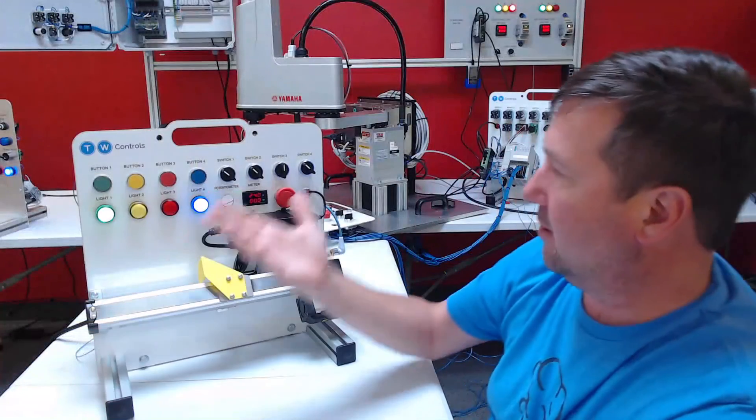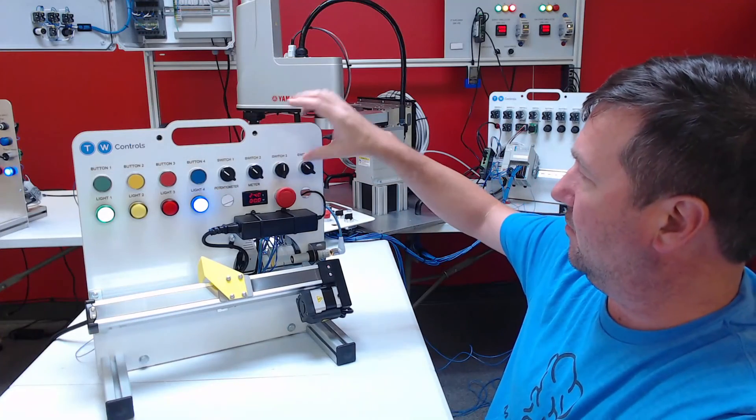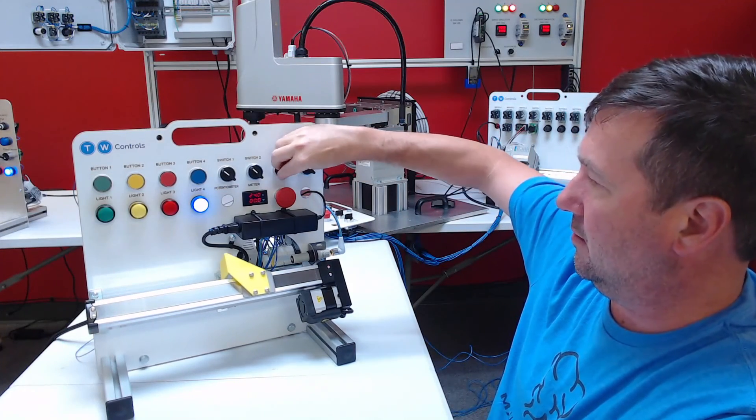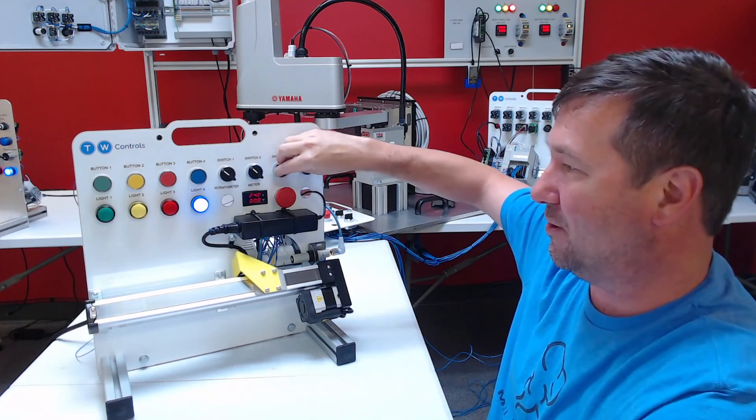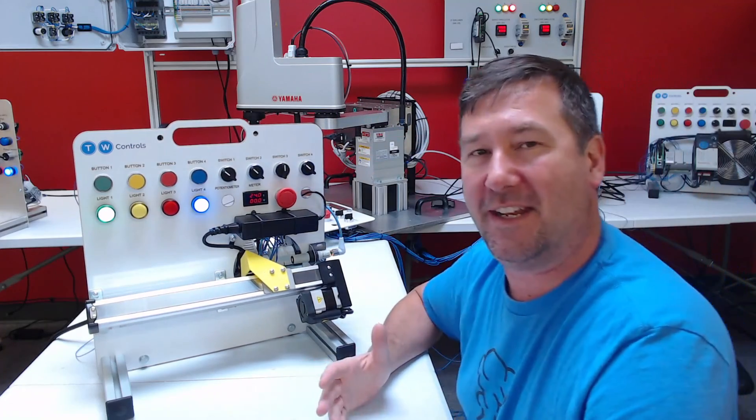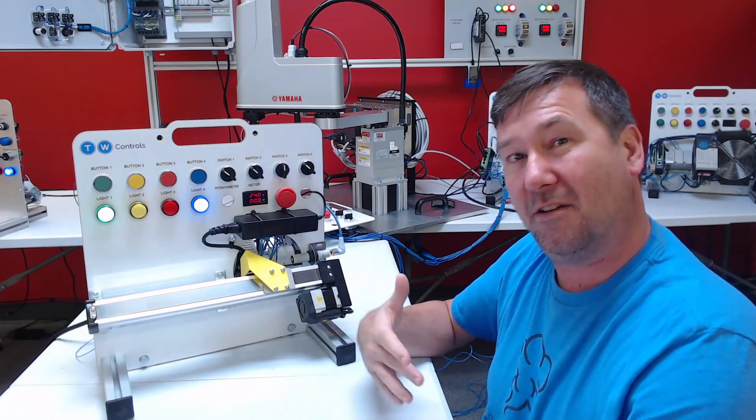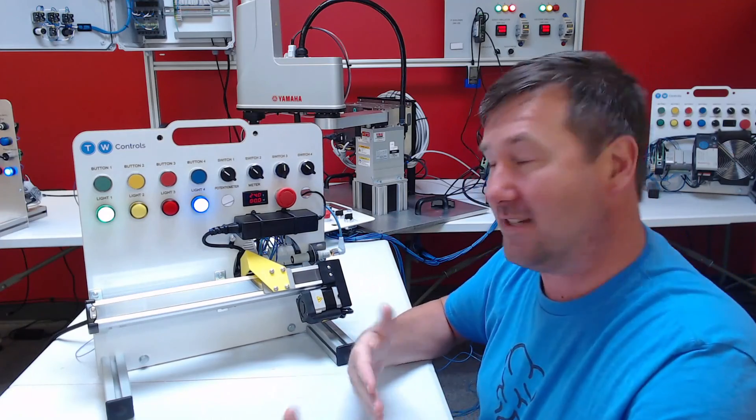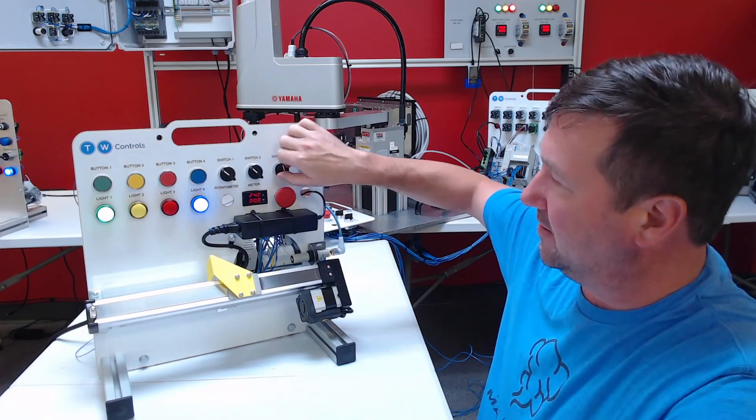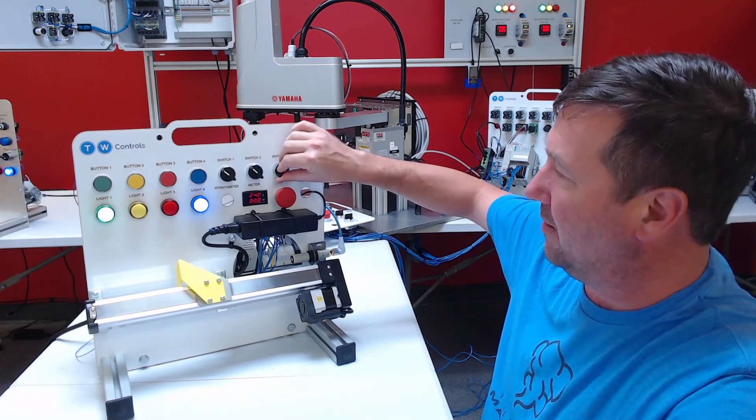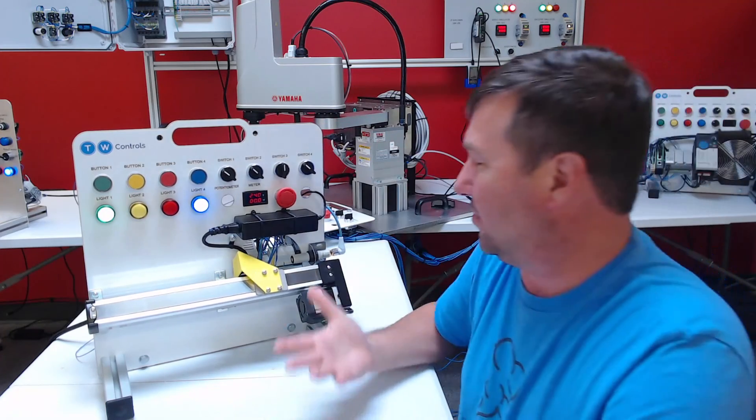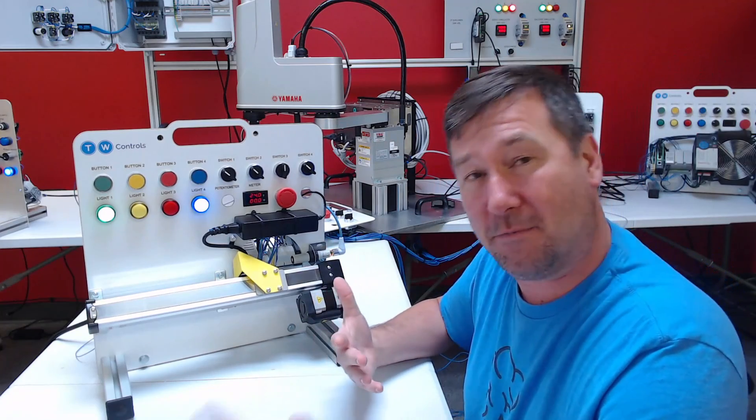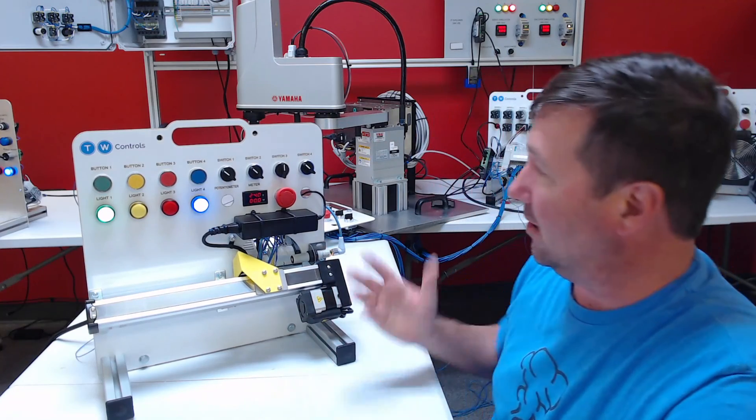And now we're going to turn on the green light if we are in position. So let's go to our favorites tab, output energize, and let's find local colon one colon O dot data dot zero. So we're going to turn the green light on as long as we're in the correct position. Put that in. And yeah, right away, we did get a green light, which is a good deal. And we should be able to just move this a little bit. And it went out.